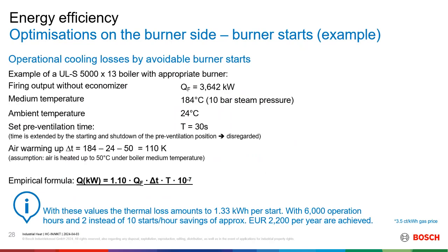I think in the last part on the burner itself, we have the purging process. Ideally, a burner should have the least possible start stops in an hour. By reducing the number of start stops in an hour, you reduce the amount of heat that you're wasting.